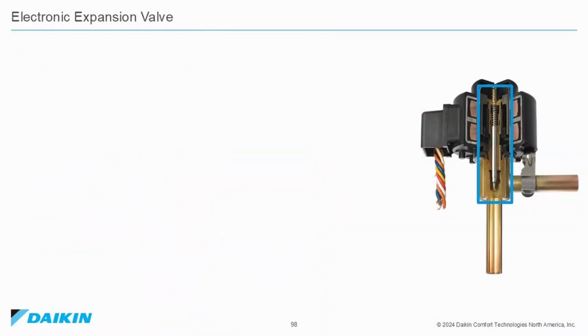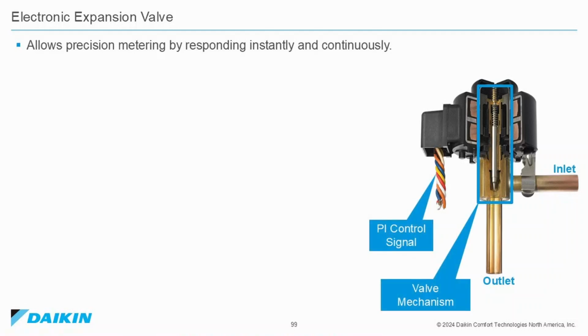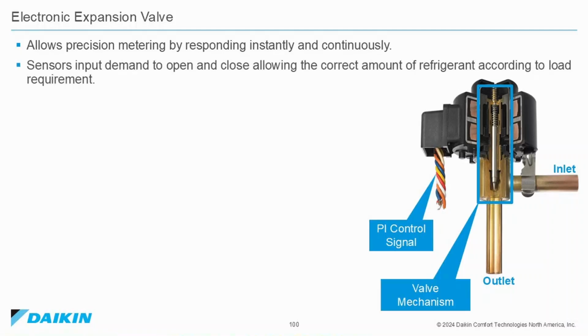The electronic expansion valve allows precision metering by responding instantly and continuously to the sensor's input demand to open and close, allowing the correct amount of refrigerant according to the load requirement. EEV motor head can be replaced without recovering the refrigerant.